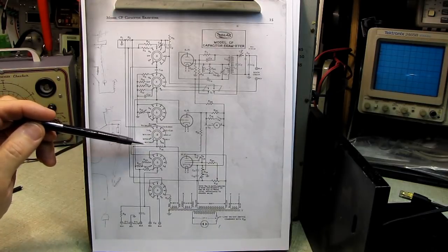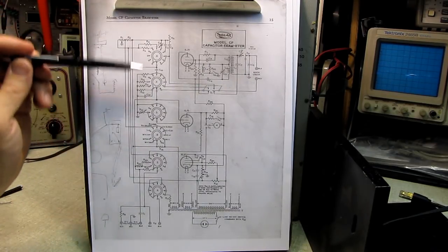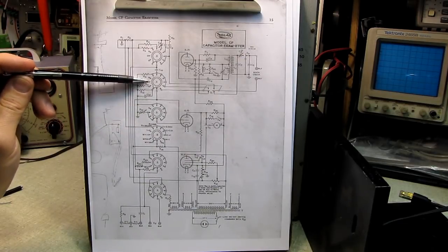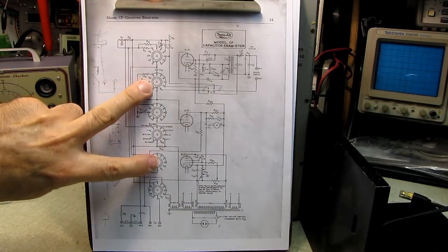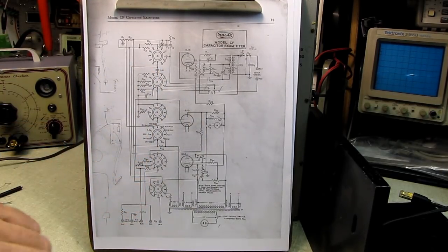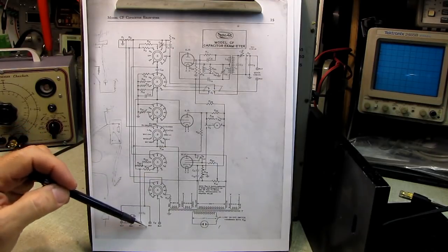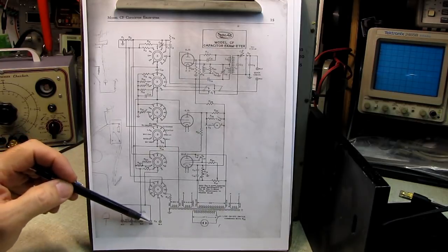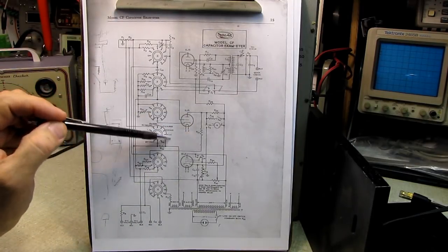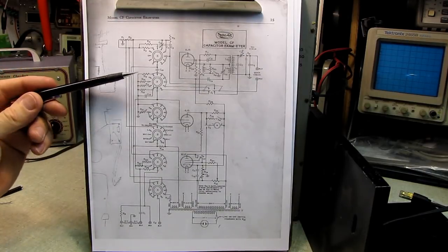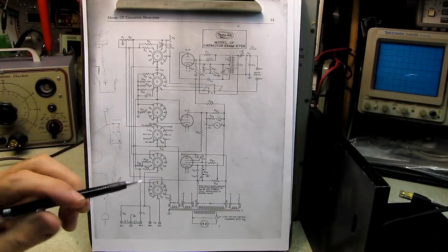Now, the switch is shown in the M times 100, or the insulation test megohms times 100 range, which made it convenient to track everything around. Looking at it, we've got our megohm range reference resistors here and here. This is the set that supplies the voltage and the voltage drop for the actual test out on the probes. These supply the ranging for the vacuum tube, the 6J5 VTVM circuit. But if this was the problem, I should be seeing varying readings, and when you went through the three range settings, there was hardly any change at all.